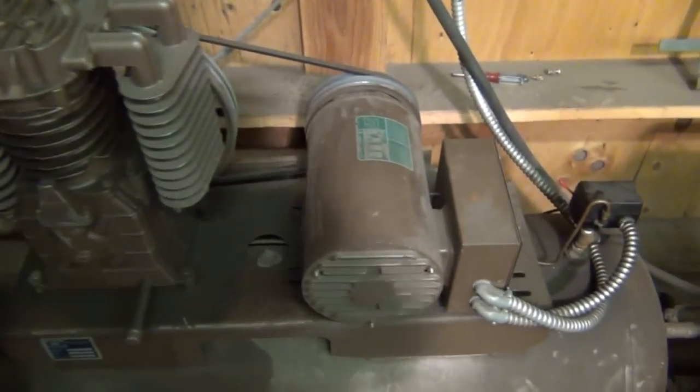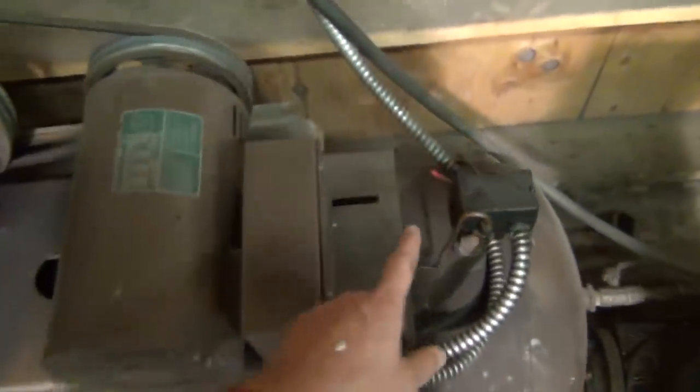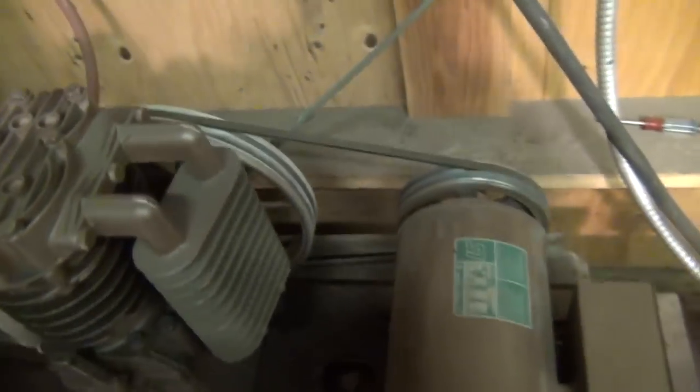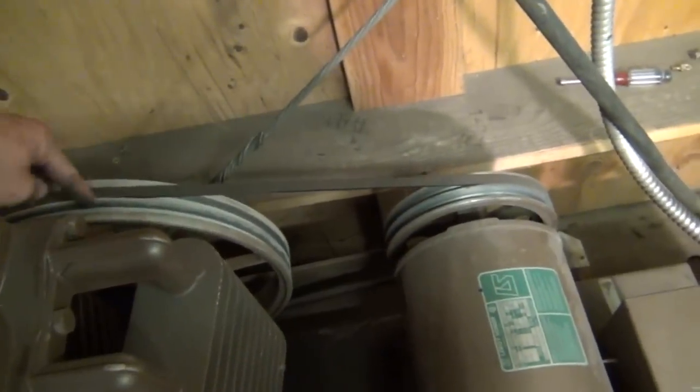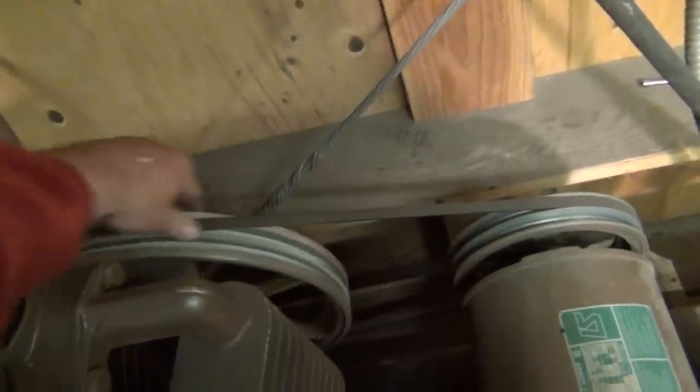Alright, now I have turned the circuit breaker back on so there is power to the magnetic contactor, but I turned the pressure switch off right here so the compressor wouldn't be trying to start up. I have also removed the belt pulley guard, and the first thing I'm going to do is just turn this thing over by hand and make sure there's no mechanical binding or anything like that that's keeping the machine from turning.